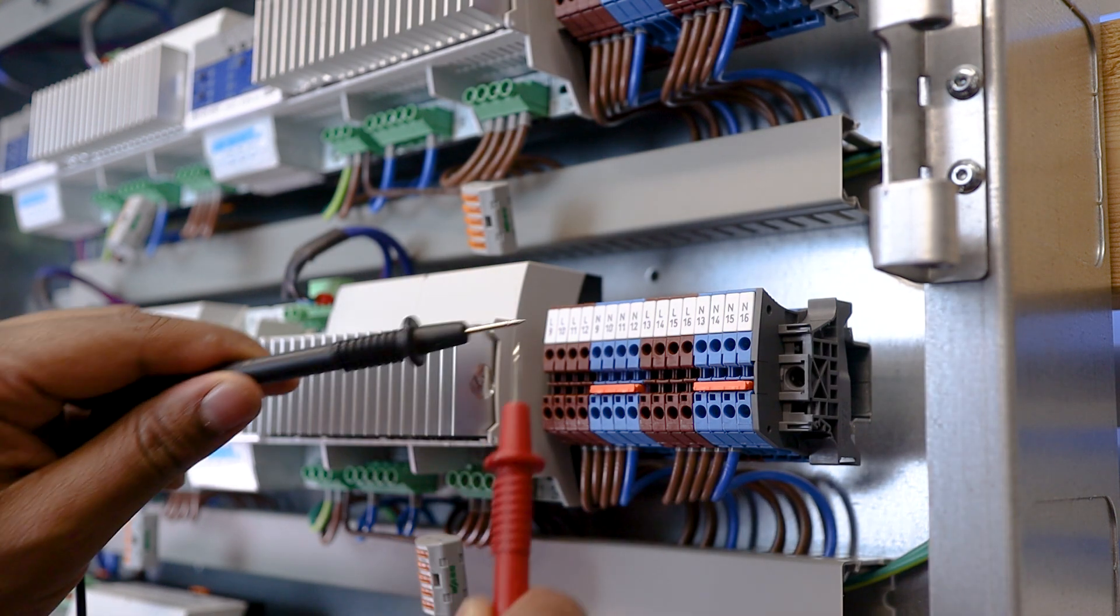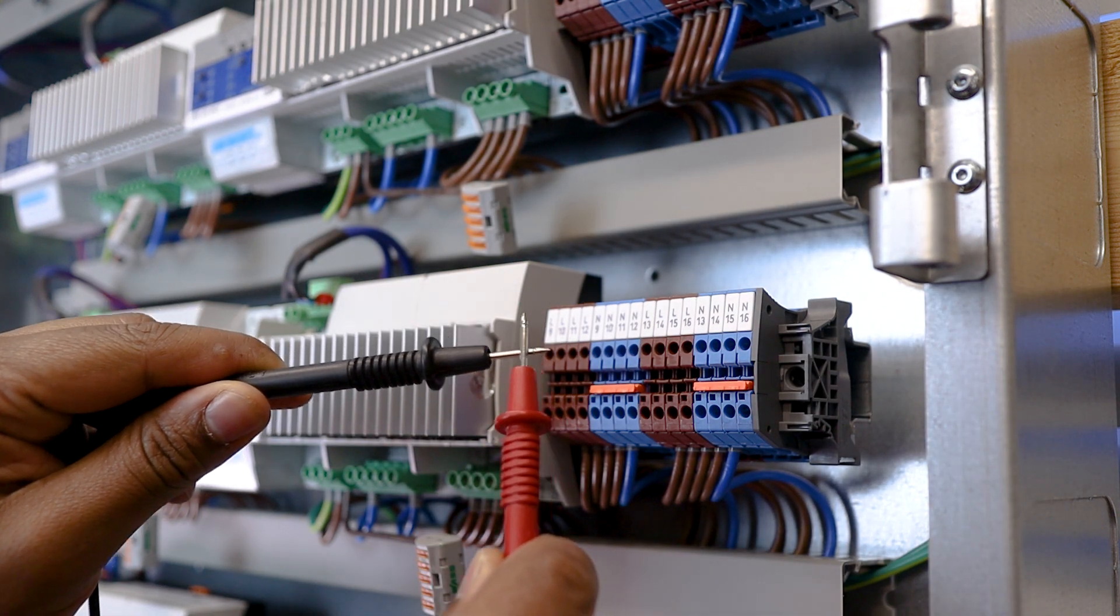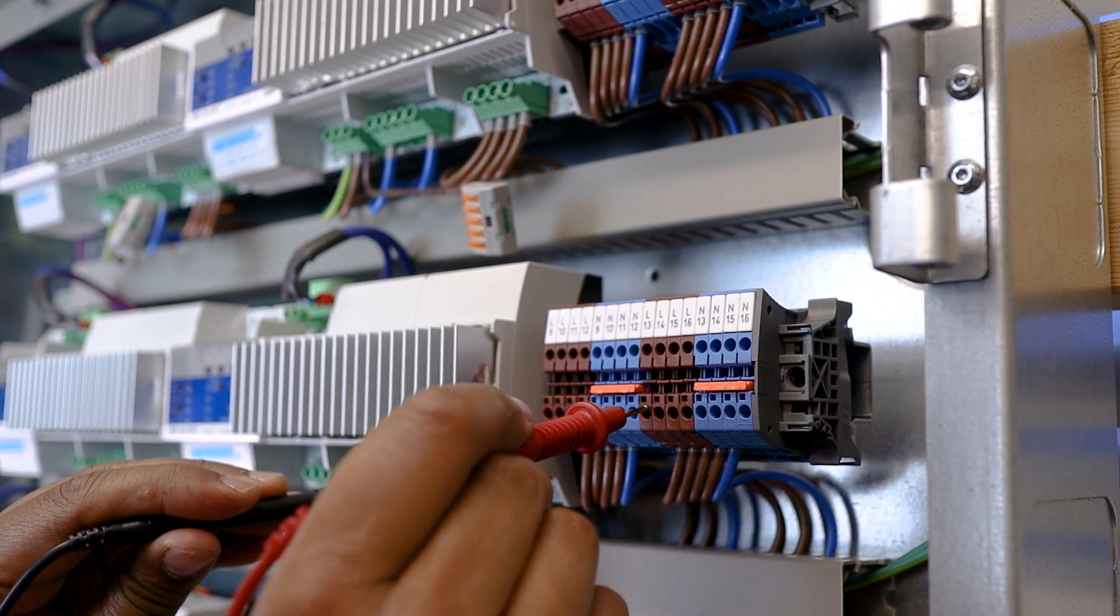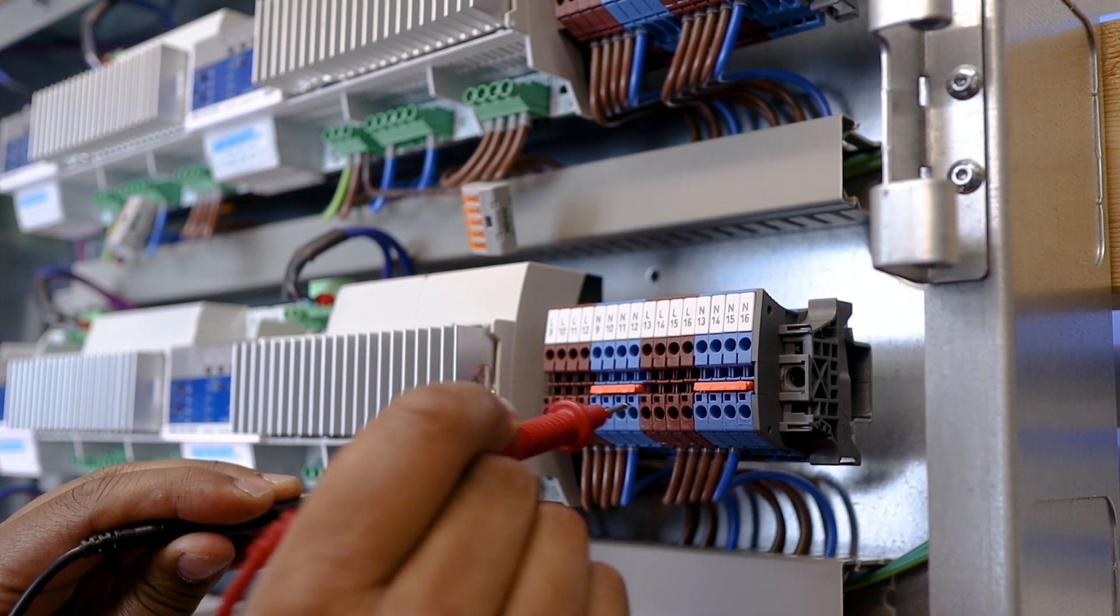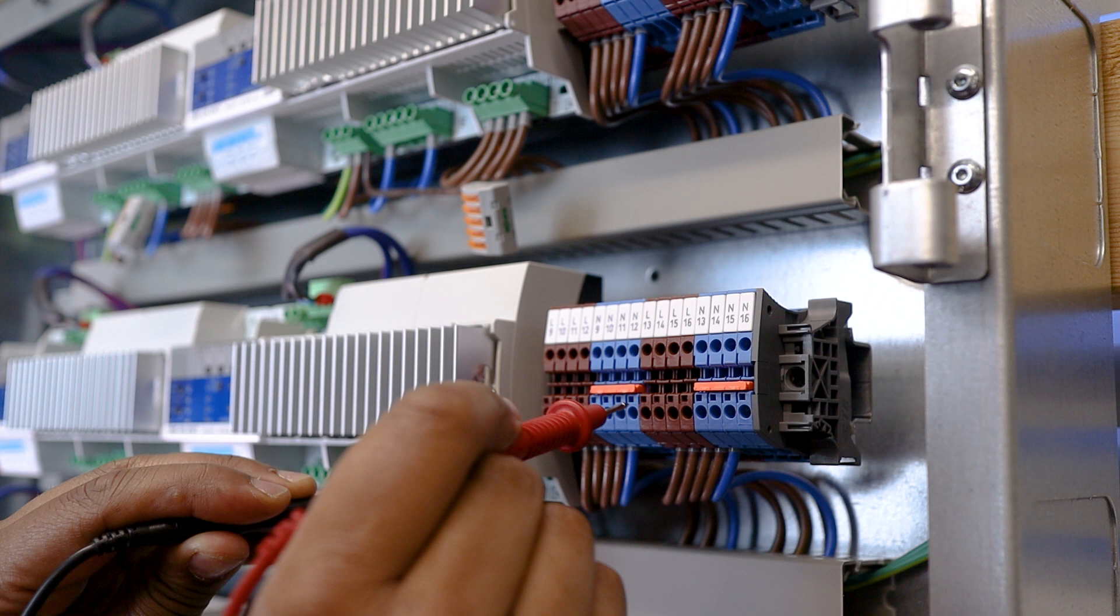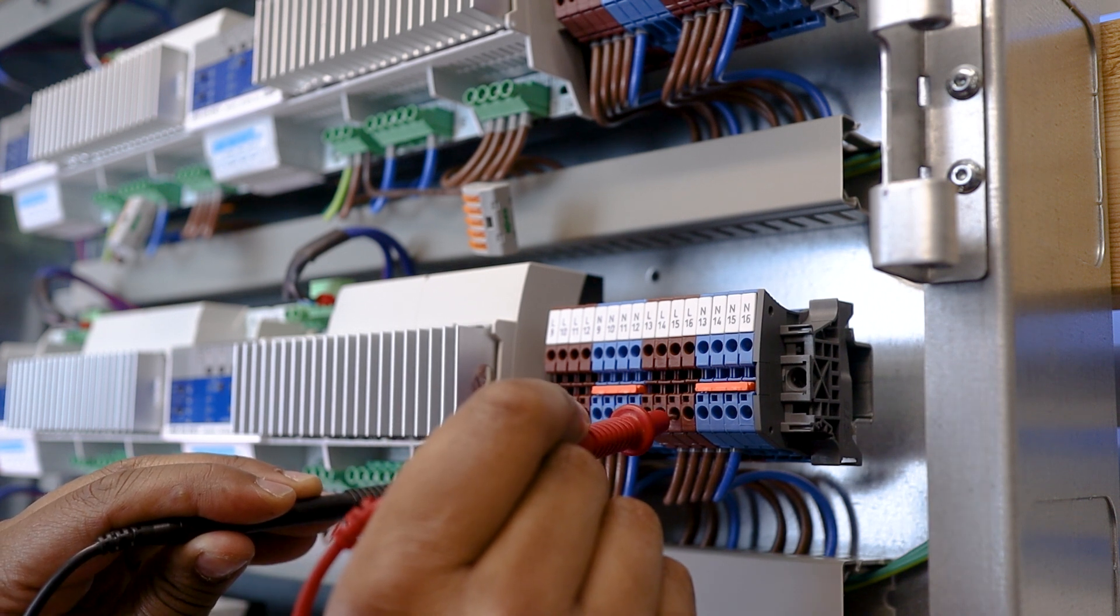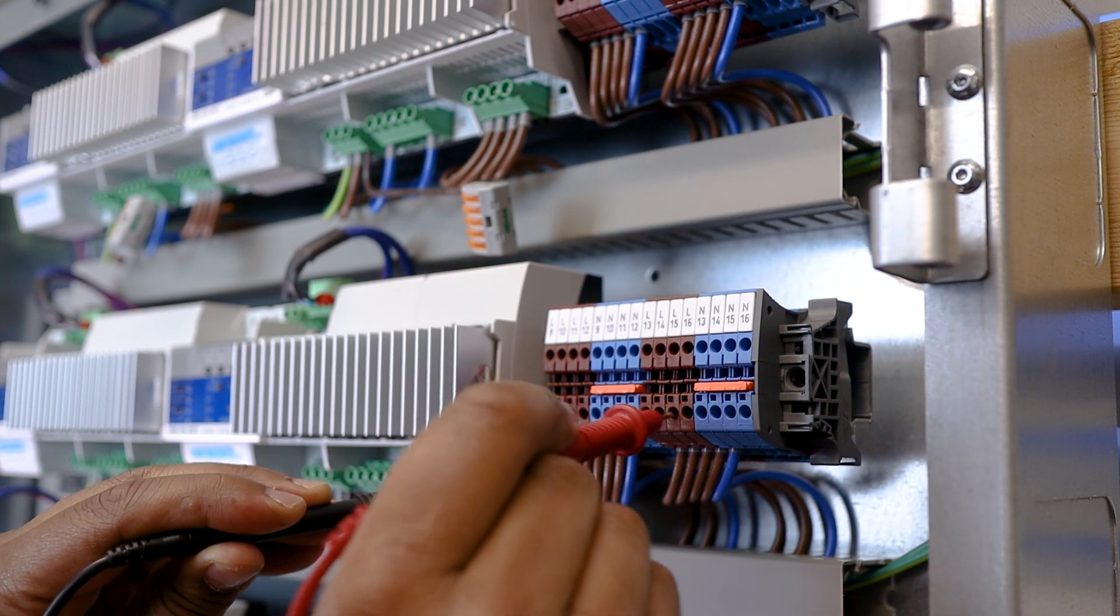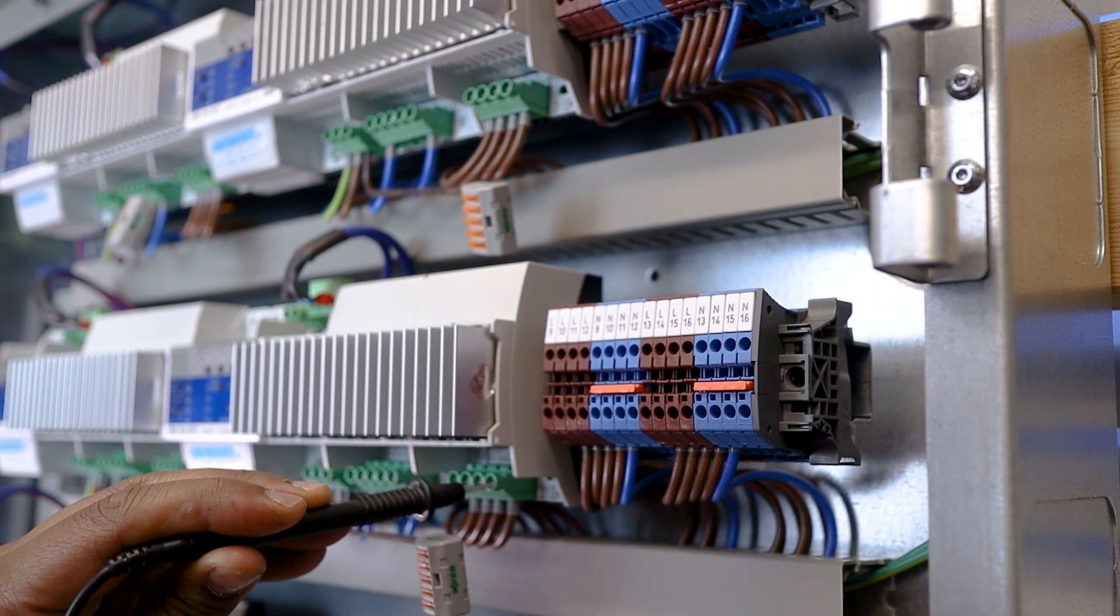Last thing, I'm going to double check my wiring before I deliver the panel to site. Just to make sure, each module output matches exactly the corresponding panel outputs, on those connector blocks here, where my lighting circuits will be connected to. The blocks on the left, match the Lutron module on the left of the DIN rail, and the block on the right, the module on the right. And I'll do this test for all the modules.